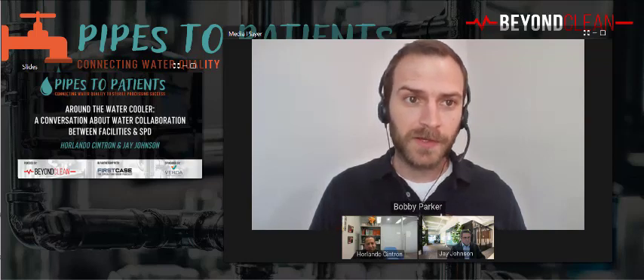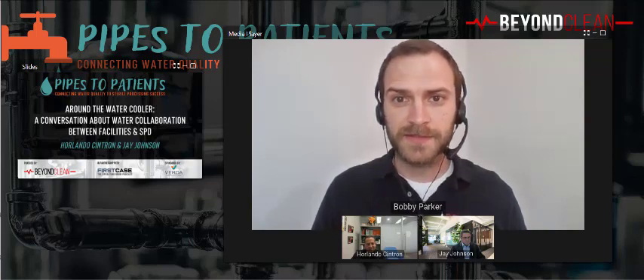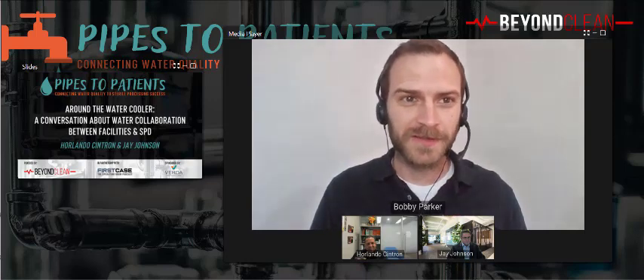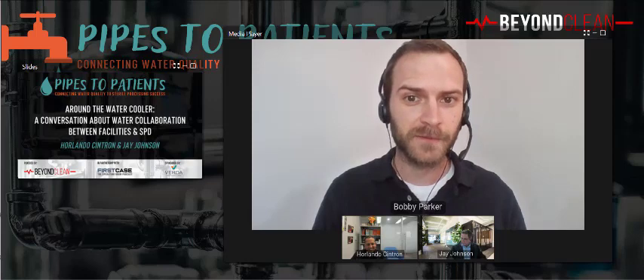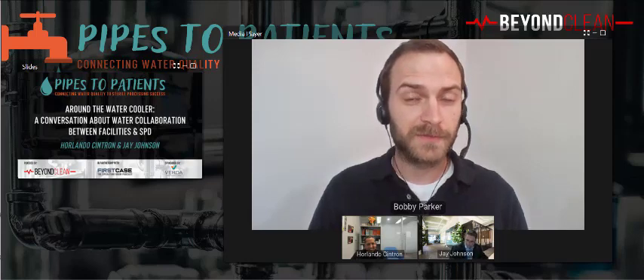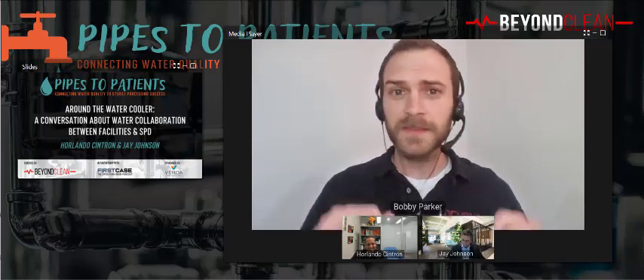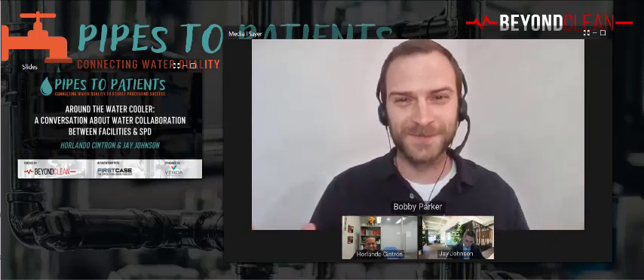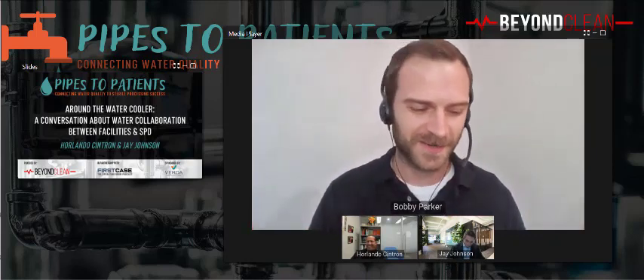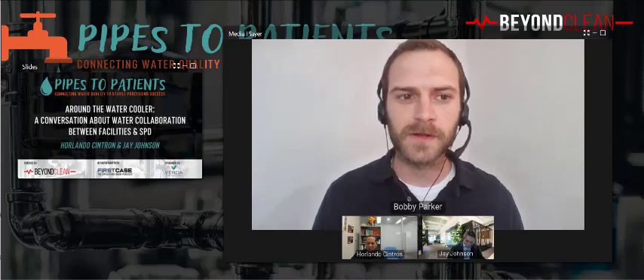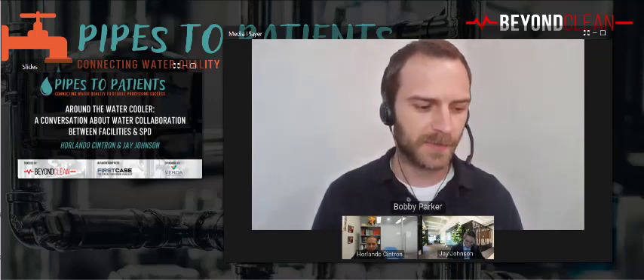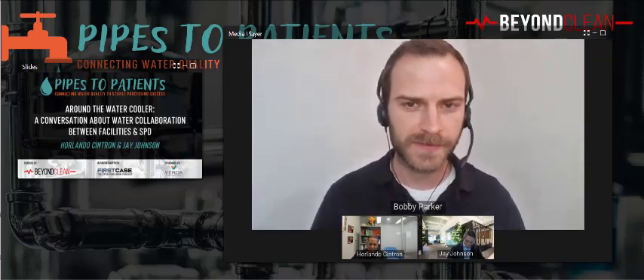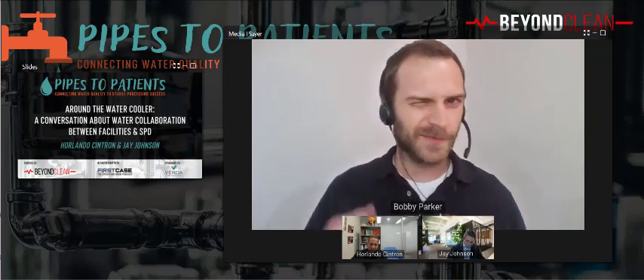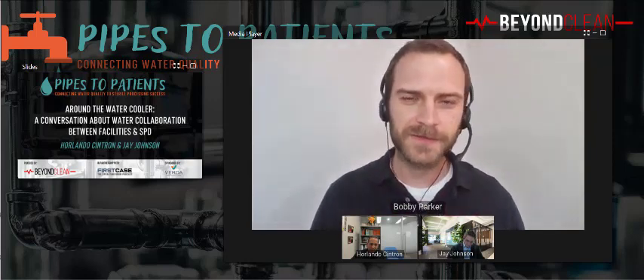But when you get the instrument brand new out of the package, that's actually when it's at its most vulnerable. So if you experience that your brand new instruments rust more than the ones that have been around for 4 years, it's for good reason. That's not to say you should expect your instruments to rust out of the washer, though. It does indicate something's wrong. But if it's curious that it's happening more with the new instruments than the old ones, it's not only that they don't make things the way they used to. It's also just the chemistry of what's going on with the makeup of that metal.